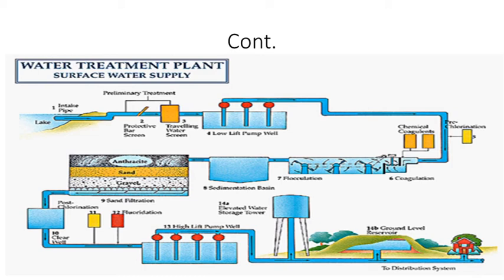Okay, so backwashing is a simple and easy process as compared to the replacement of the layer of sand. So that is the method of cleaning: replacement of sand layer up to 1.5 to 3 centimeter in case of the slow sand filter. And similarly, the method of cleaning for rapid sand filter is backwashing.